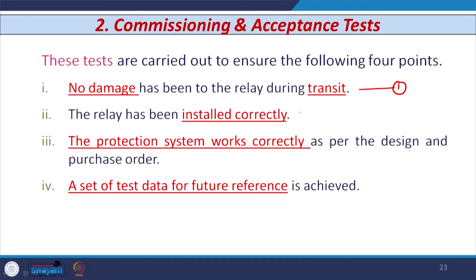The second point is that the relay has to be installed correctly. As soon as I receive the relay, I have to install it, and I have to check certain timings on the relay. So, operating time and operating current need to be checked, and I have to verify the operation of the relay as per what is given on the nameplate of the relay by the manufacturer.